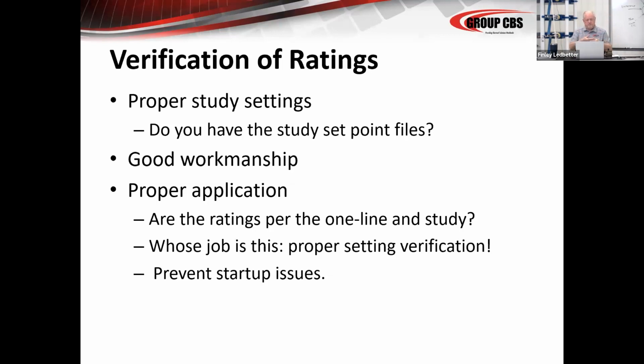You pass water through a valve. If the valve can't handle the pressure, it bursts. Same thing with the circuit breaker. You try to close the valve off, open a circuit breaker, there's a potential for problem if your IC rating is not right. The voltage class is the maximum voltage that can be applied to it. The frame size is the maximum current it can handle. The continuous current rating is the value you have the breaker set to actually handle and watch below its frame rating. So the continuous current rating cannot be higher than its frame rating. I've seen that as well.